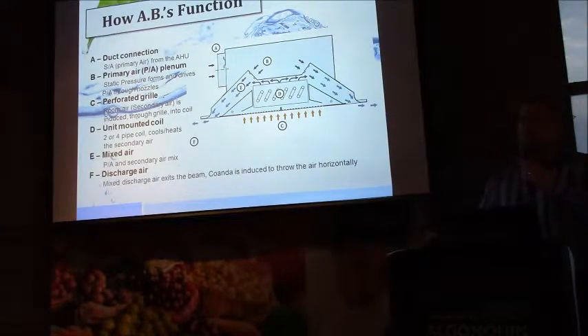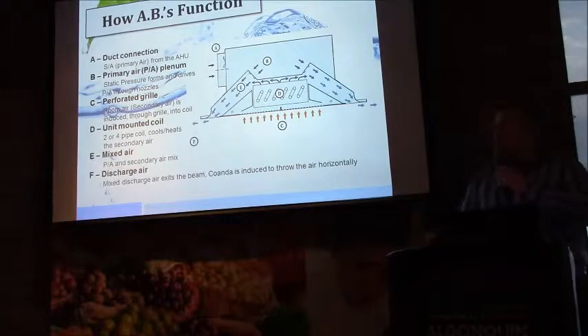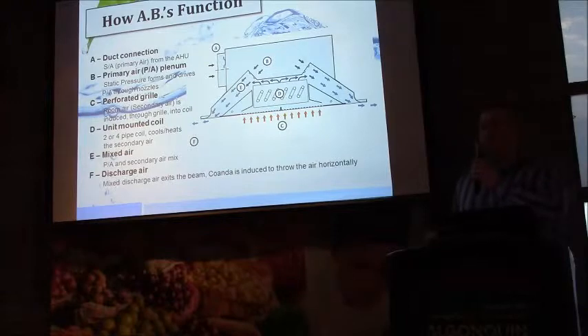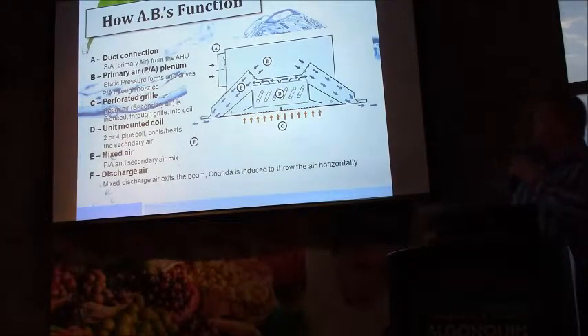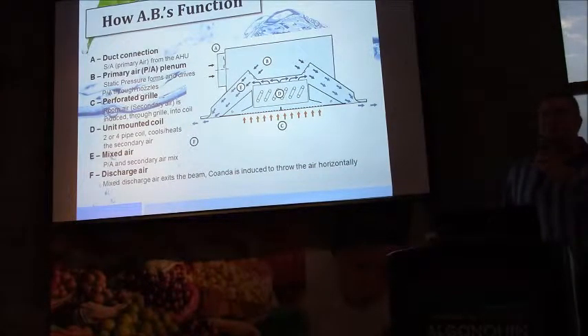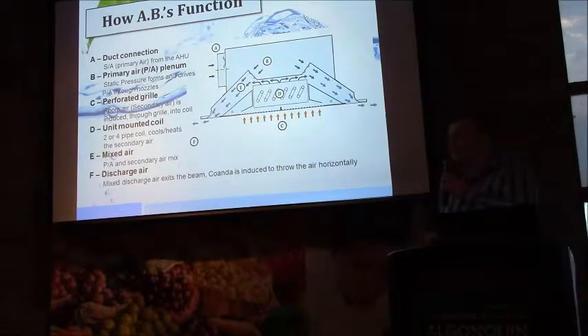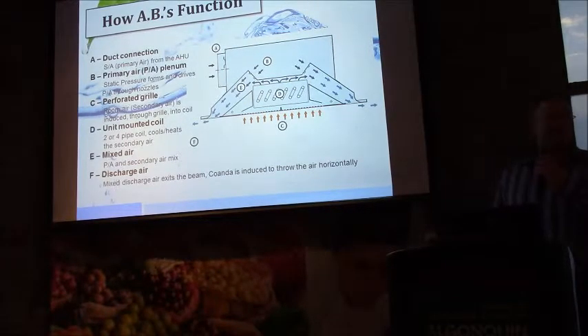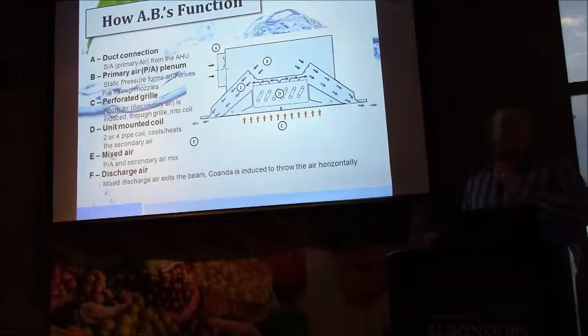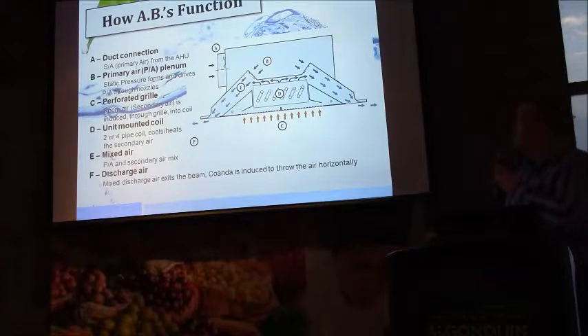So we're managing the sensible loads in the space separately from the ventilation requirements of the occupied zone. And the way these work is essentially the primary air, which is processed separately from the room air, is pressurizing the plenum at B. And the plenum pressures that you might expect to see in that pressurized plenum is between, say, 3/10 of an inch to an inch of static pressure, 70, 75 pascals to 250, roughly, for those of you that prefer metric.